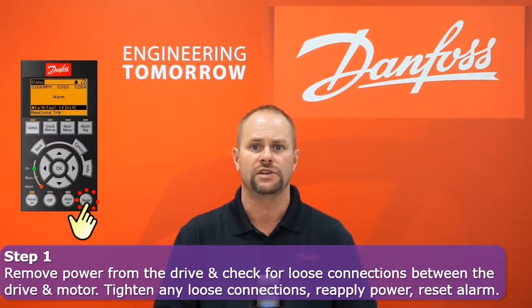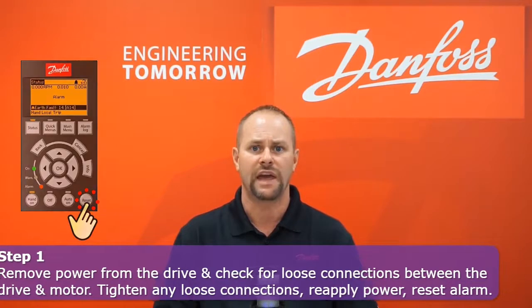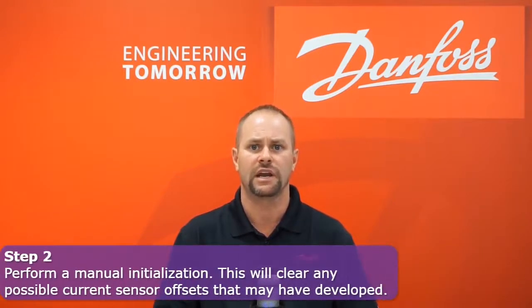If the electrical connections are found to be solid, a manual initialization is recommended at this point. This procedure will clear any potential current sensor offset that may have developed. Please refer to the following slide for instruction on that process.